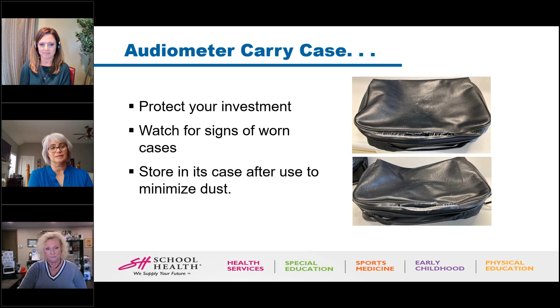So in summary, for any of your equipment that you might be using, you want to clean and disinfect it after use. Also, if you've got one that's battery operated, I know we didn't mention this earlier, but you want to take those batteries out before you're storing it. If anybody's stored their machines of any kind with batteries in them, those batteries can start to ooze or something can happen, and that is also not a really great way to keep that investment protected. Calibrating the headphones yearly, we talked about that, and storing in a location that is between 30 and 95 degrees, with humidity considered.